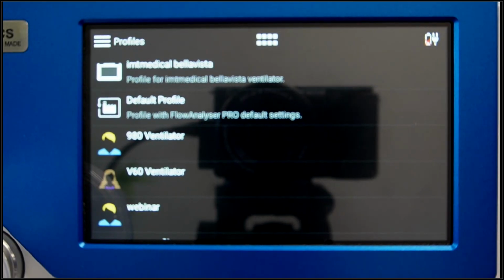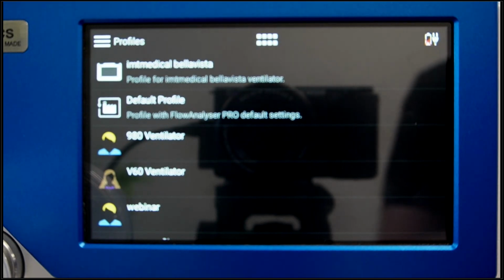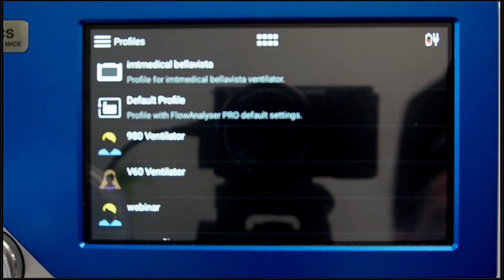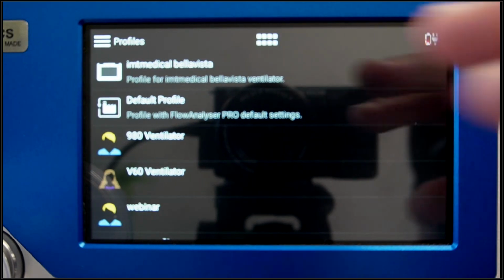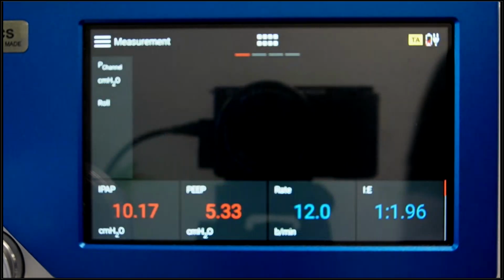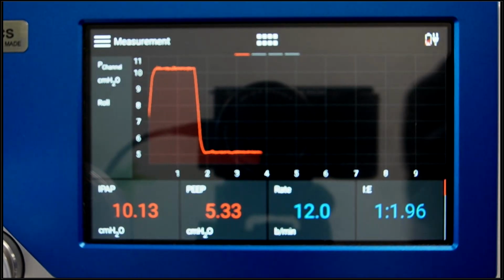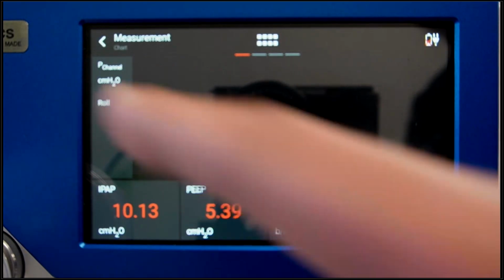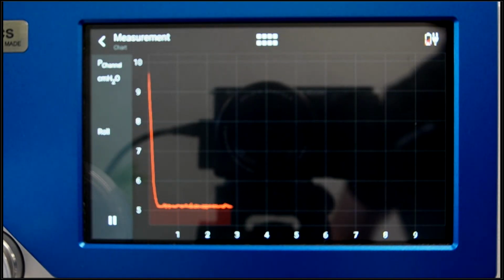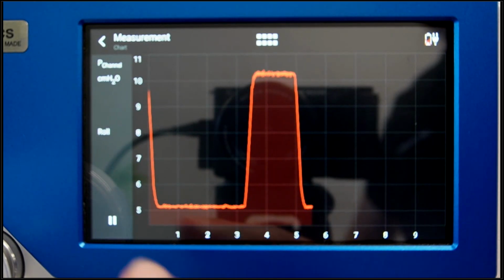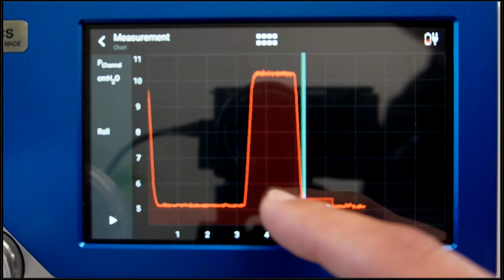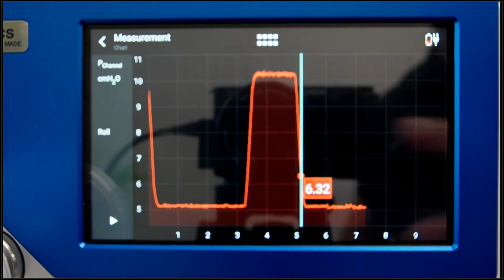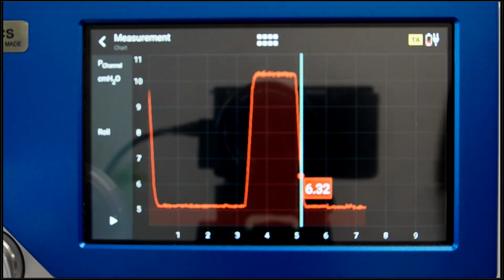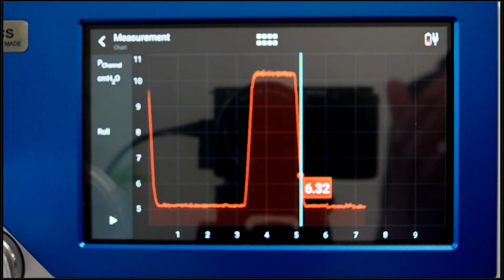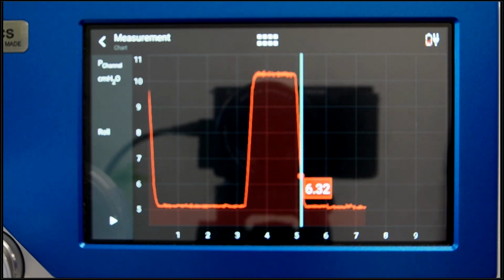The second practical tip is to use advanced automation and aids as features that your gas flow analyzer might offer. So watch out for things like real-time waveform analysis, as you can do here on this device. For example, if I enlarge my pressure waveform here, I can see it on the big screen here, and I can even pause my waveform and then measure values here. So this can be very helpful if you really want to find a suitable trigger signal and to see what trigger levels make most sense for my application.